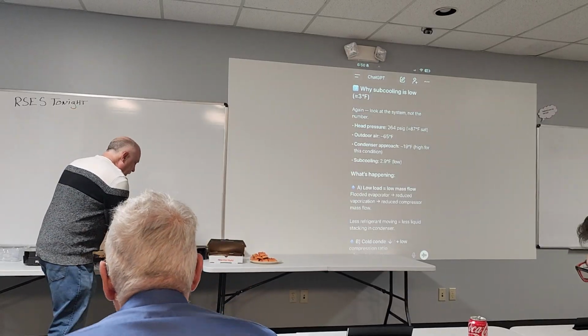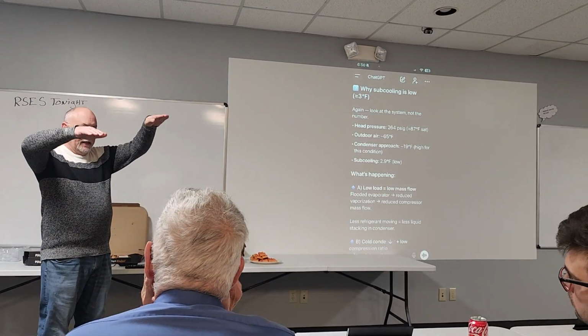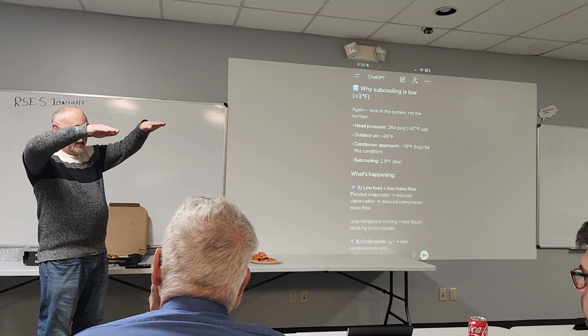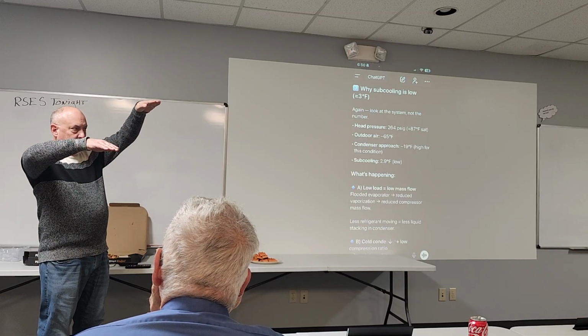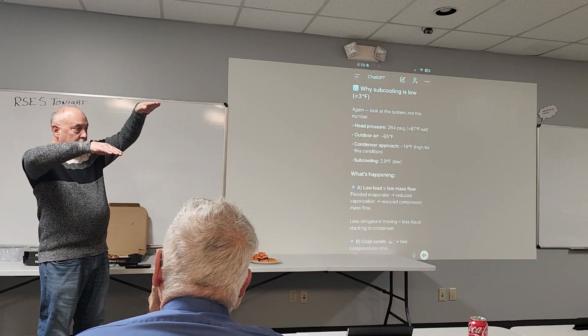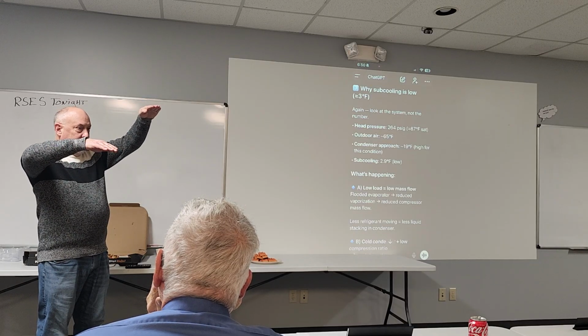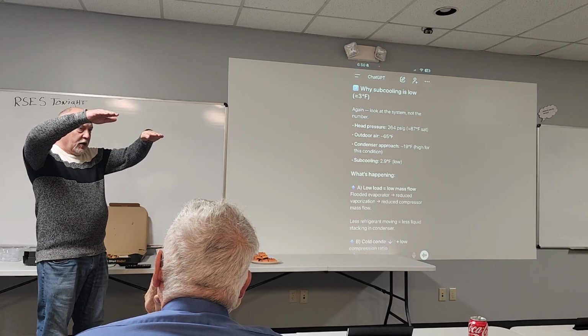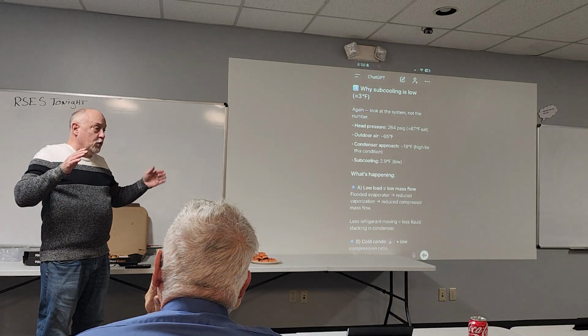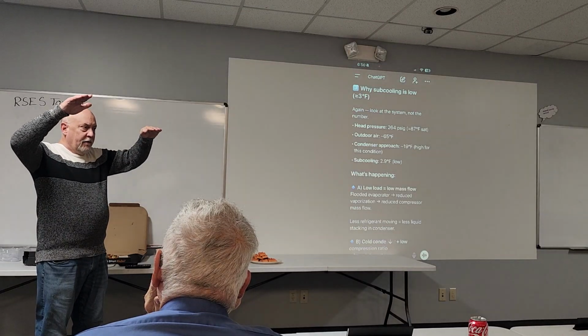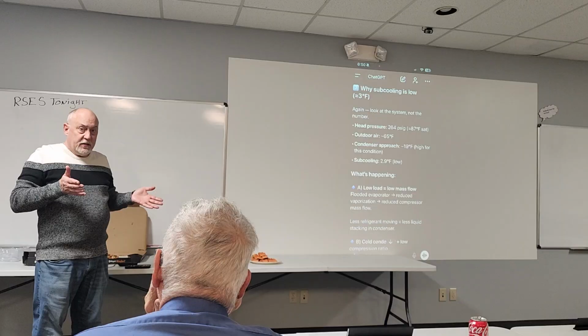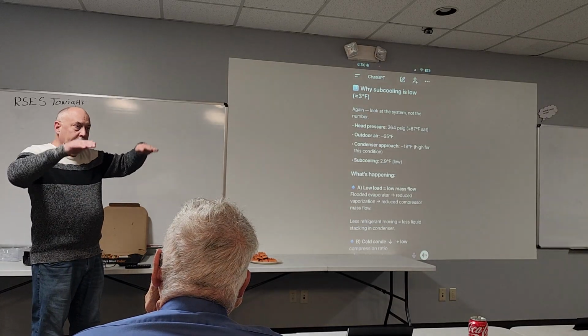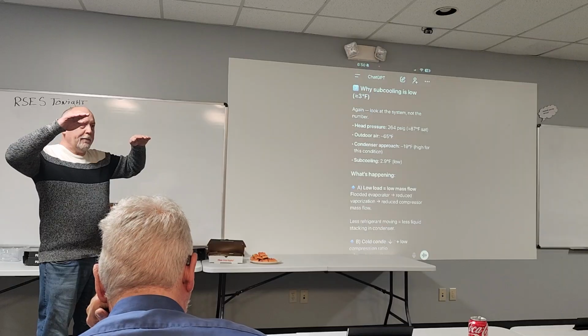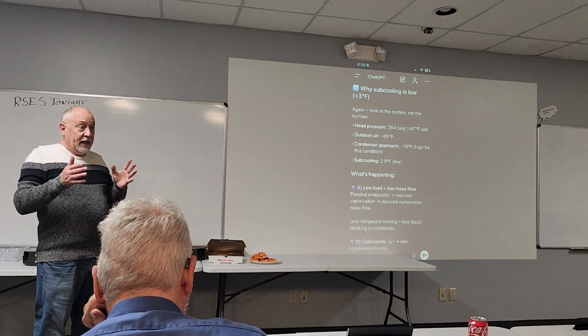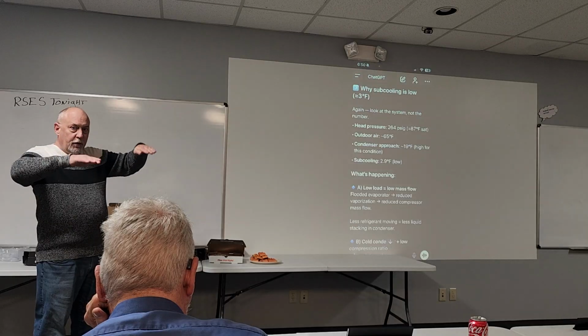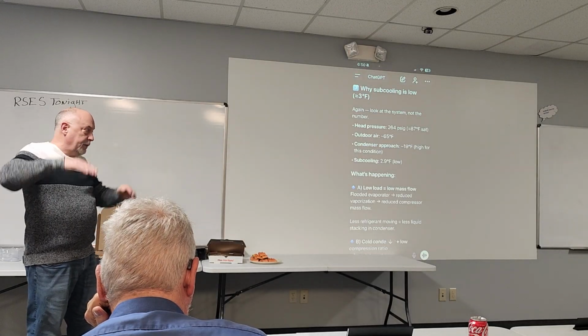I always think about a balance beam when I'm looking at a fixed orifice system. If I push down on the condenser, I'm going to raise the refrigerant level in the evaporator. When I raise my refrigerant level in the evaporator, my superheat goes down, right? Because the refrigerant has less time to boil off. I can also do it the other way and flood my condenser and starve my evaporator. If I don't have enough differential pressure, like if it's warmer in the house than it is outside, I'm going to have a very high superheat target. That's where it gets to like a 30 degree superheat target, because I don't have the differential pressure required. Now, we always charge by superheat, but there's also actually a target subcooling. So as we move refrigerant around, the subcooling goes up and down and the superheat goes up and down.